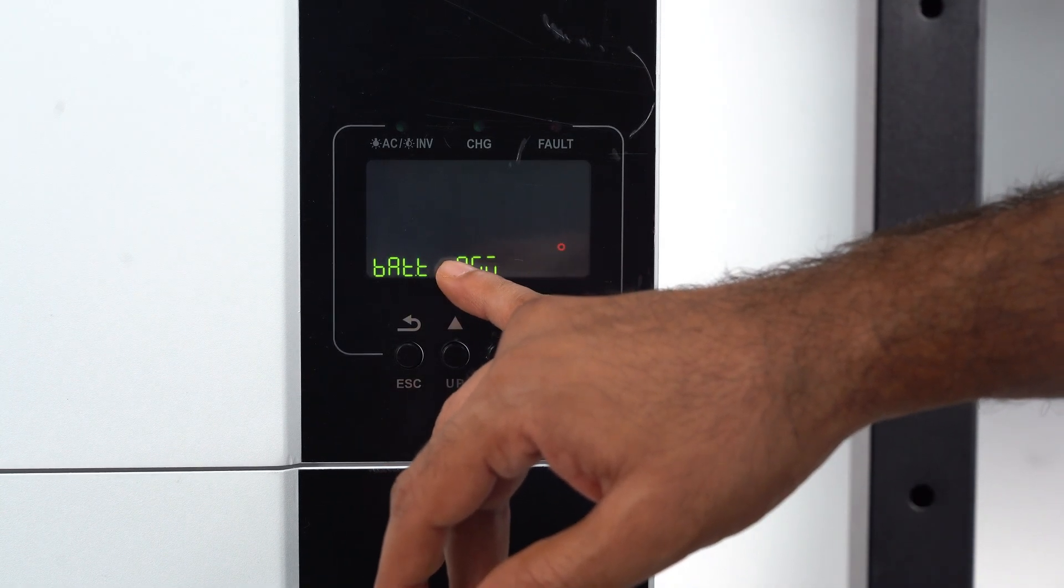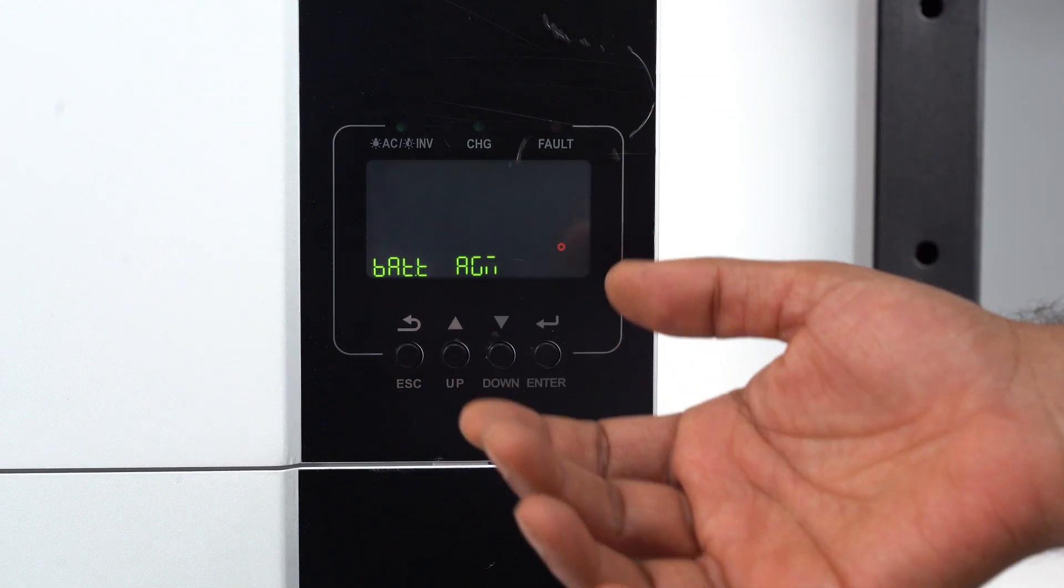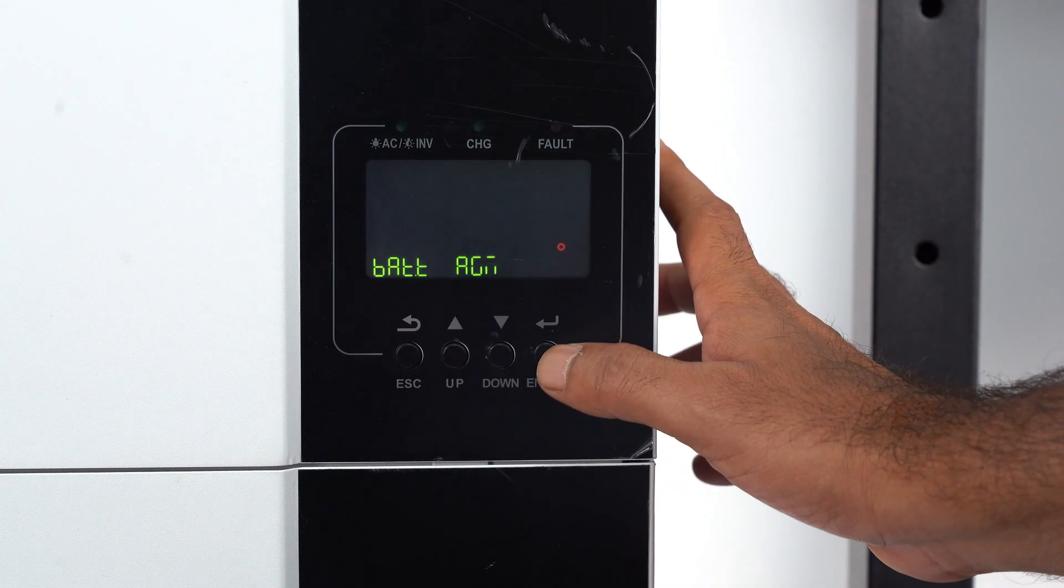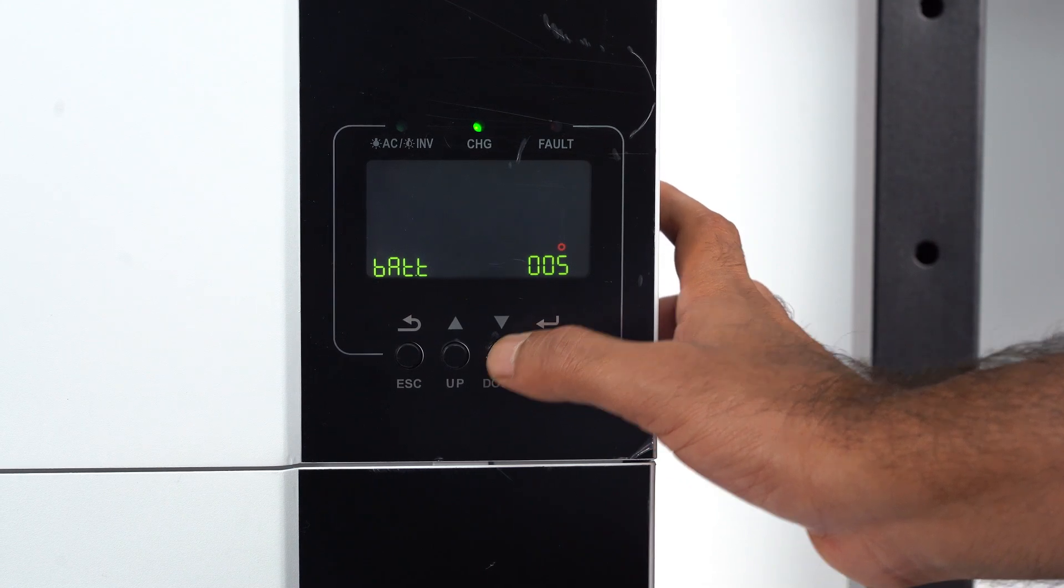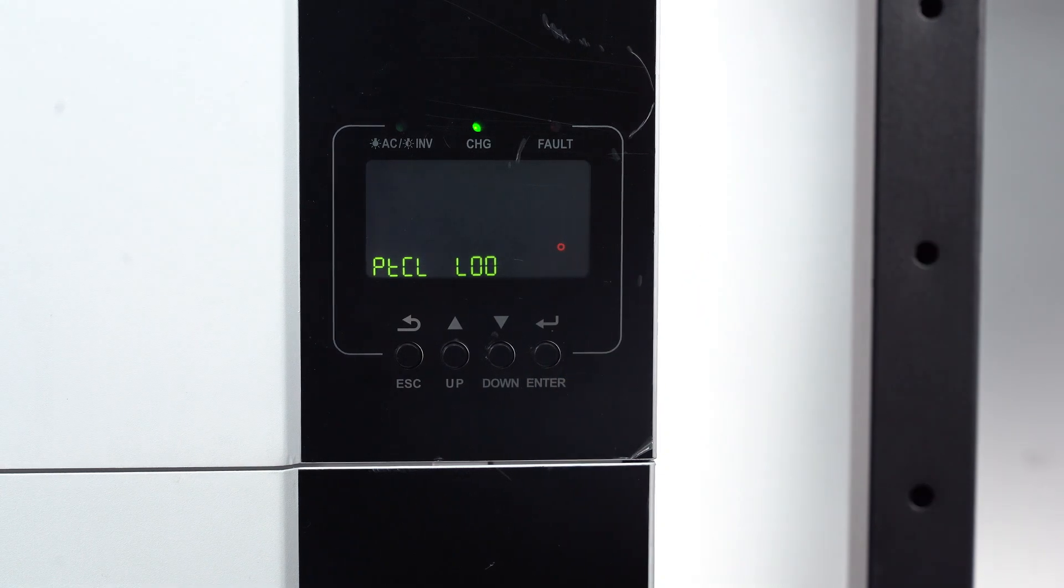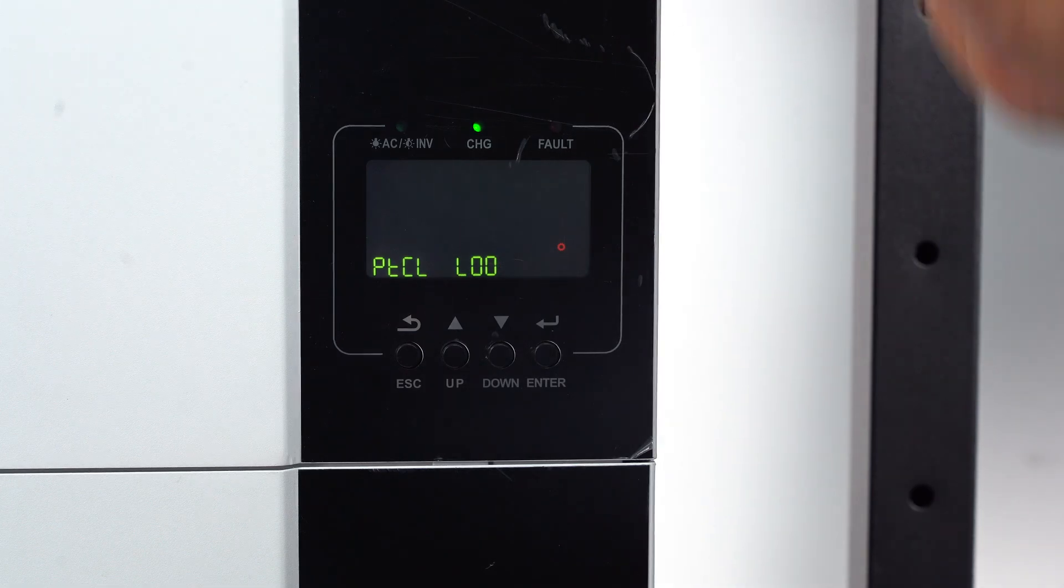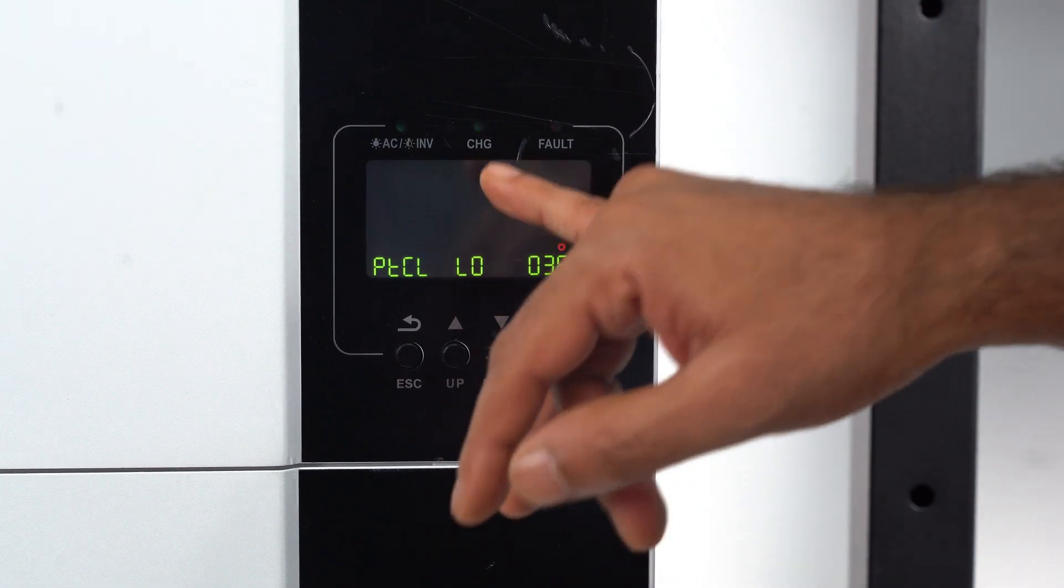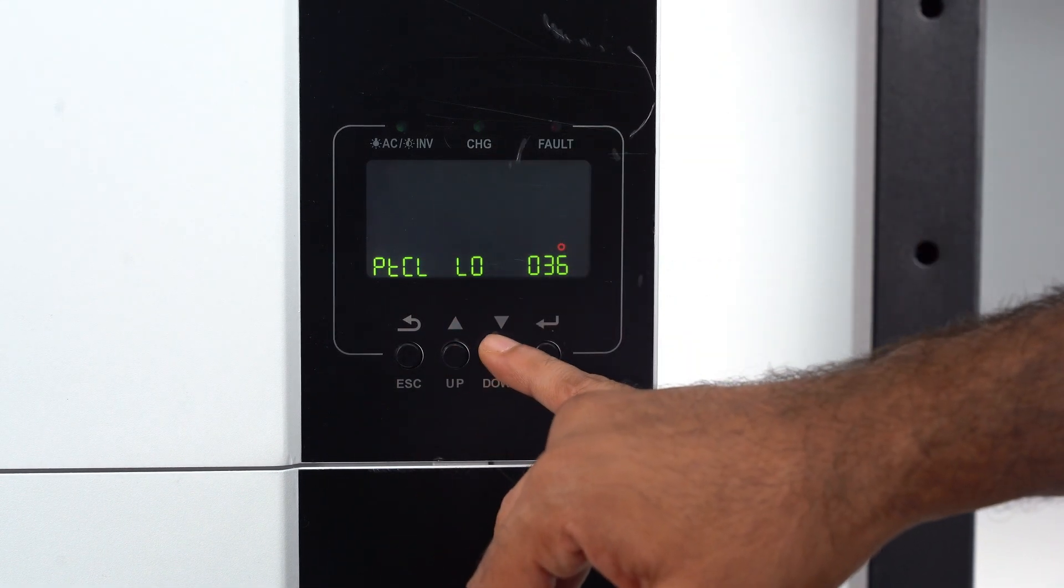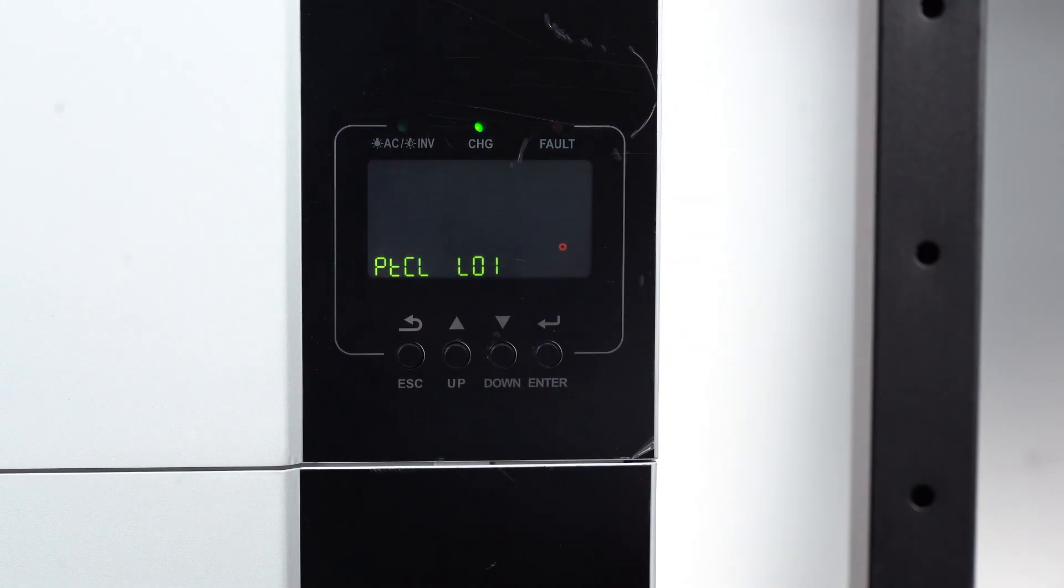Once we are in battery, you can see this AGM battery already by default, which is every inverter's default battery as AGM. We need to change it to Li battery. Here is Li battery and press enter. 36 is a communication protocol of Growatt inverter. Press enter. We need to select the communication BMS communication port which is 01.